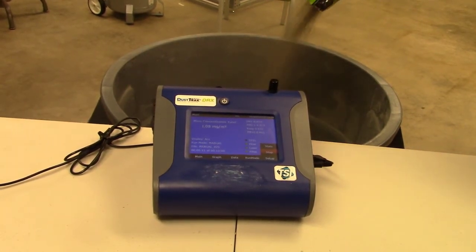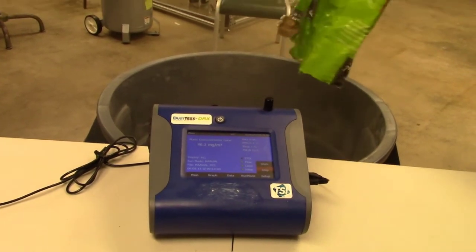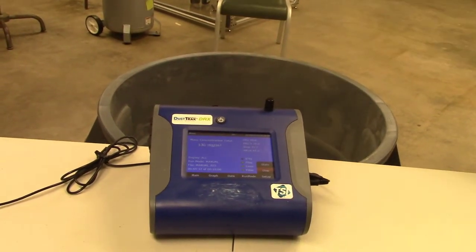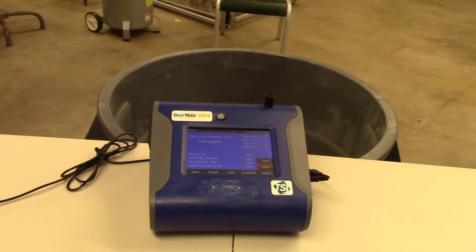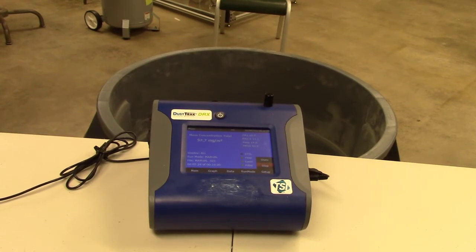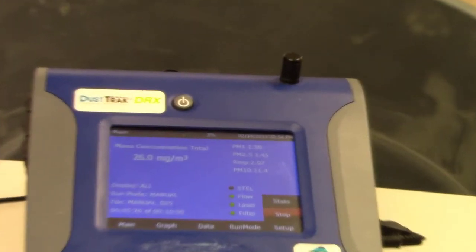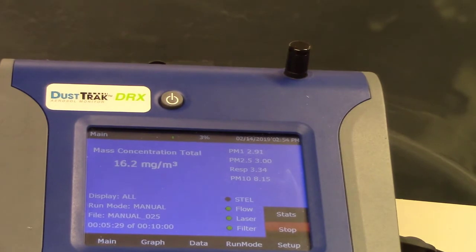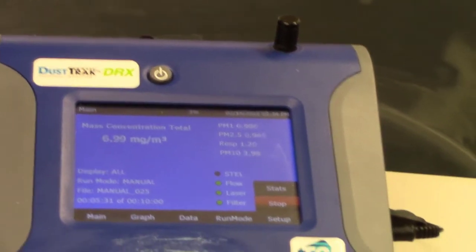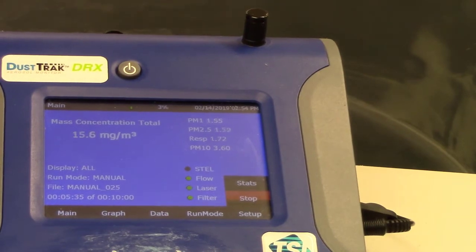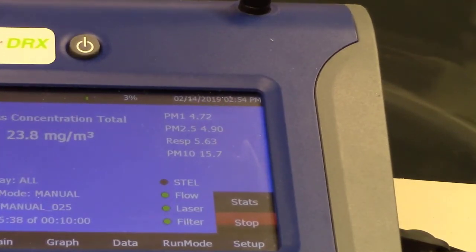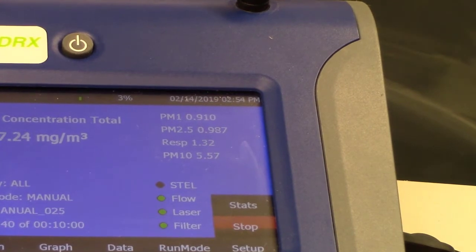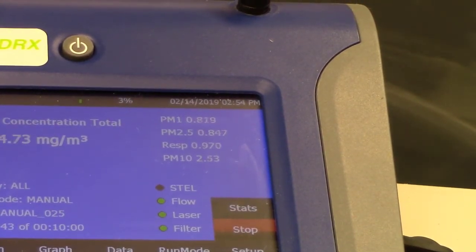As dust is being generated, the instrument is picking and measuring dust particles and recording the data on our monitor. And like I said, the mass concentration is going to be constantly changing as the different particles are being generated. As you can see our total mass concentration is changing in our different mass fractions. So for the sake of time, I'm going to jump onto the eighth minute mark to see what is happening.